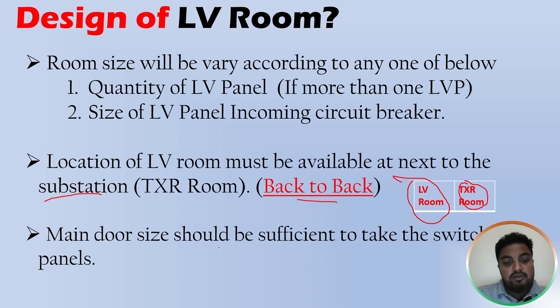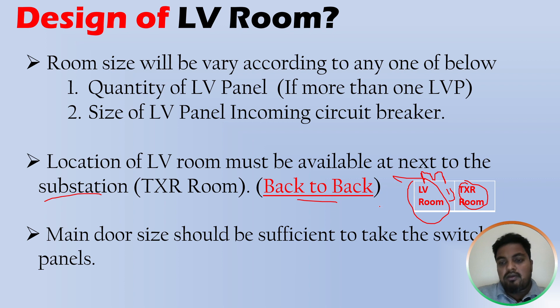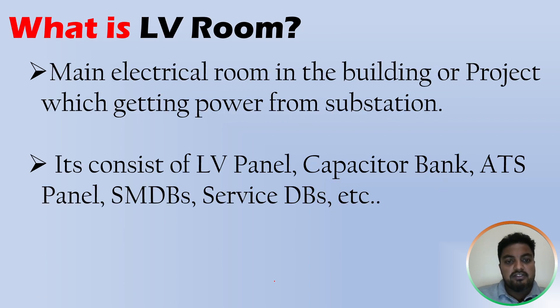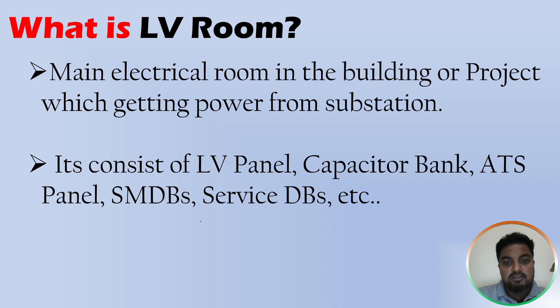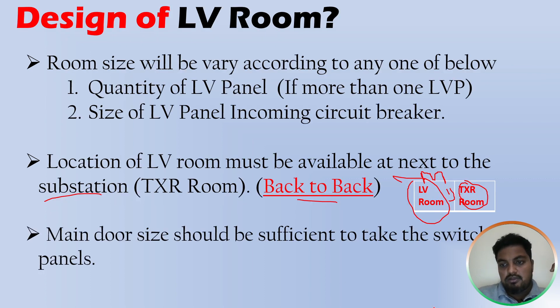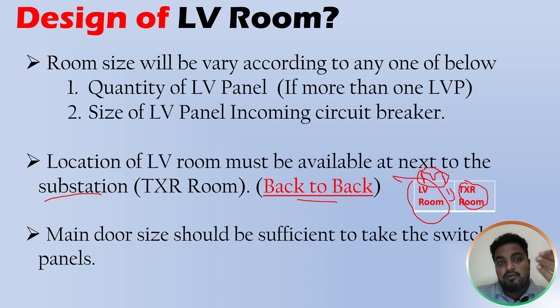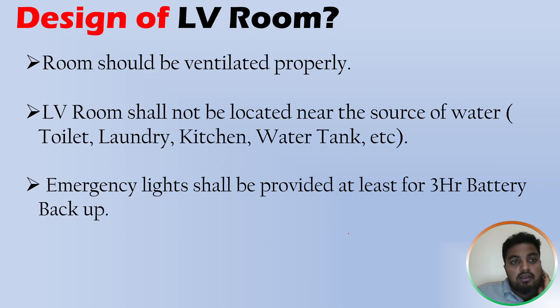Another important point: the main door size should be sufficient to allow the switchgear panels to be moved inside. When you are designing the LV room, you have to consider the door size. The LV panel and capacitor bank are large items — the door must be wide enough so that all panels, including the LV panel and capacitor bank, can be brought into the LV room. So when designing, make the door as large as necessary.